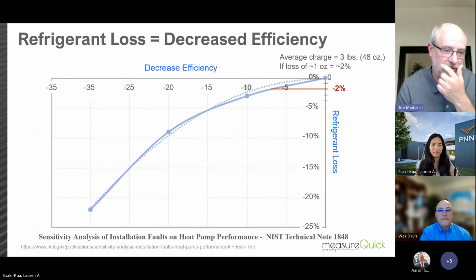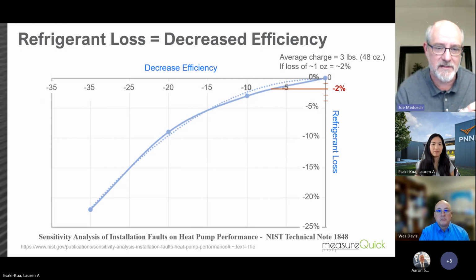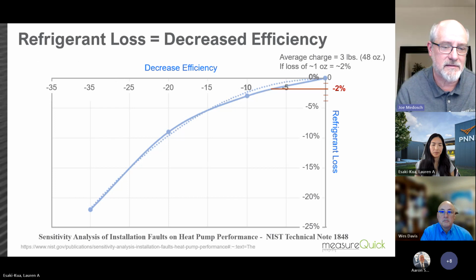So we talked earlier about the challenge with the charge. If I'm losing a little bit every time somebody connects their gauges—because they always have to connect their gauges, psh, psh, psh—it doesn't take much to have refrigerant left in the hoses and a little bit lost. At 2%, which is most of what happens in just one or two visits to the house from the hoses, 2% is equivalent to about a 6 to 7% decrease in efficiency just from servicing the equipment.